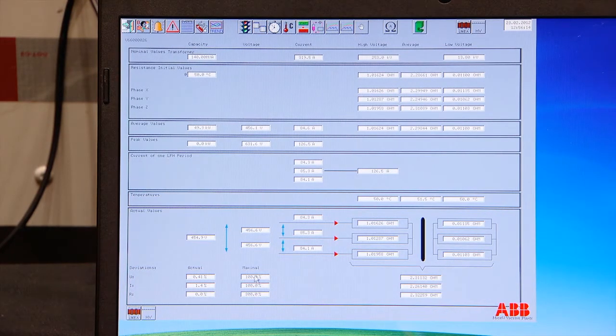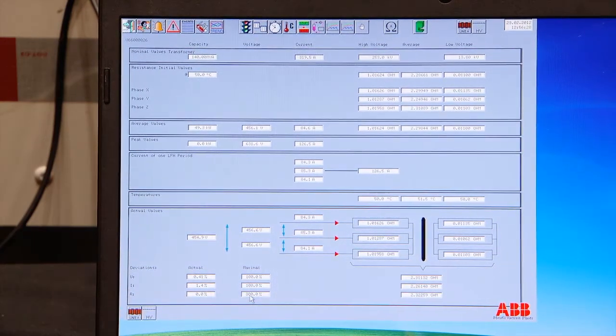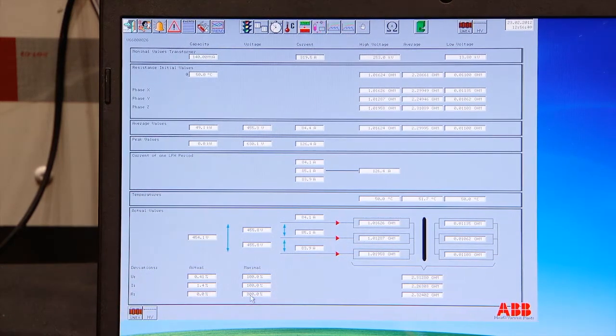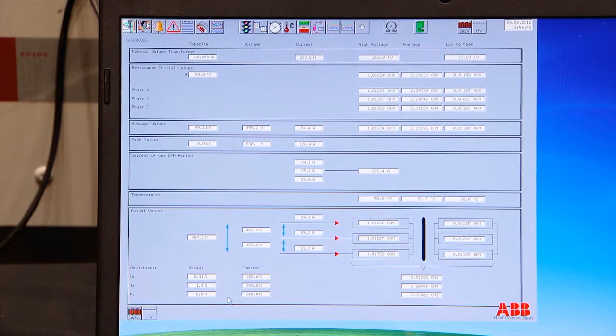You also have an alarm level. Now this one is set very, very high. Alarm level is normally 10, 15% deviation. When you get this deviation, you should check cables, you should check everything externally, all connections. You should also check the short circuit bars, that you don't have an issue there that could affect it. Lastly, there can be an issue inside the transformer, that something has fallen loose or you have a short circuit, maybe by the PT100 if you have damaged the insulation or whatever.